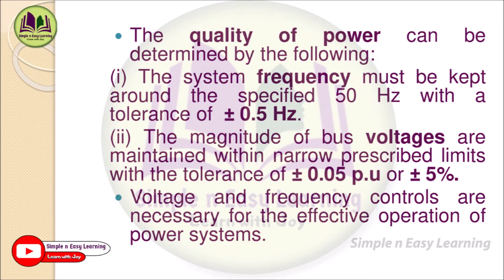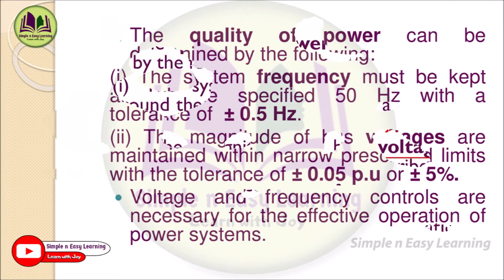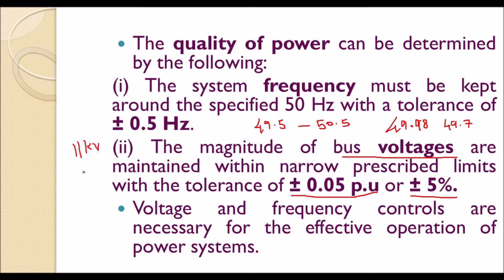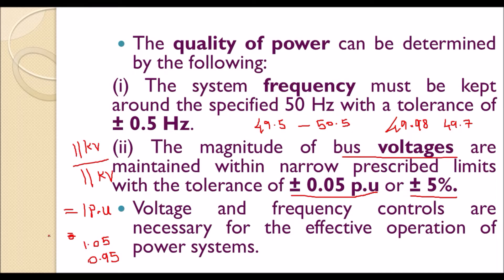The magnitude of bus voltages must be maintained within prescribed limits with a tolerance of plus or minus 0.05 per unit. Bus voltage is ideally maintained at 1 per unit — for example, if the actual value is 11 kV and the base value is 11 kV, the per unit value equals 1. The allowable range is 0.95 to 1.05 per unit. Within this range, good quality power is delivered, making voltage and frequency control necessary for effective power system operation.